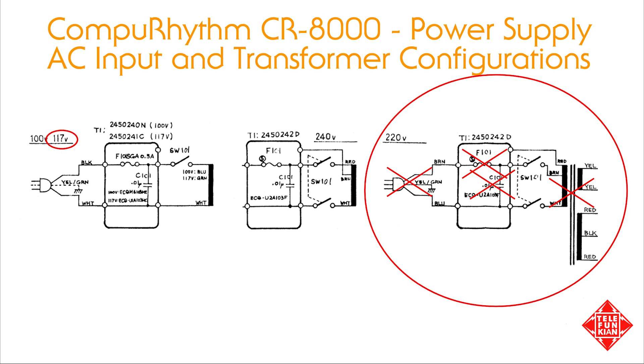Each of these transformers has 2 independent secondary windings that provide independent AC sources powering the 3 main DC rails used in the instrument. As we'll be converting this instrument for use in North America, we'll be dispensing with the power cable, the aforementioned capacitor, and the transformer, reusing only the power switch and the PCB housing the line capacitor and fuse in this part of the power supply.